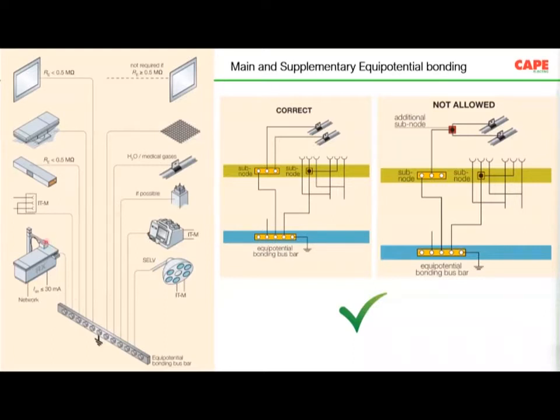Then you can see here some of the biomedical equipment are connected. The medical IT system is connected to the bus bar. The cable management system is connected to the bus bar. The floor mats, electrostatic mats, or some mats, if available, are also connected to this particular bar. The lights, the monitoring system, the medical gas, and the other extraneous conductive parts such as the wash basin, all the metal parts in that location are connected to a common bus bar, and this is called supplementary equipotential bonding. One of the first and foremost electrical safety requirements in a medical location is to have supplementary equipotential bonding.